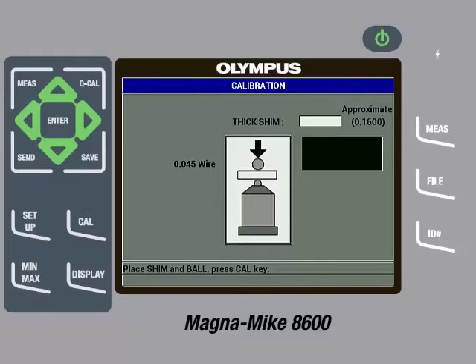Then, screw the top cap down enough so it is secure and the wire is aligned properly. Then, place the wire and calibration fixture on the probe and gently pull down on the sides of the fixture to make sure the probe tip is in contact with the shim. The instrument will start displaying a thickness value. Once the reading is steady, press the cal key.